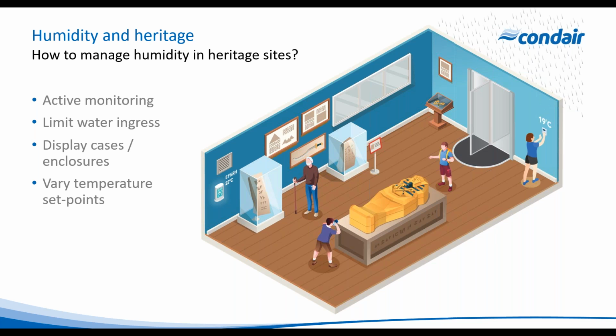Now, we may need various temperature set points to stay within humidity range. And as we've seen, temperature is intimately linked to humidity. So when there's the ability to lower temperature set points in the winter or raise them in the summer to remain inside the humidity range, that is a win-win situation.